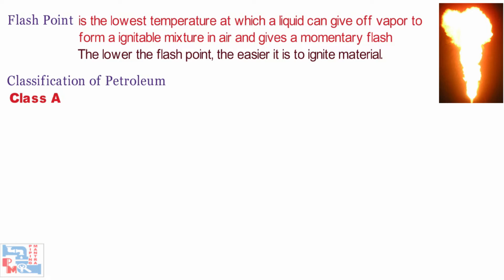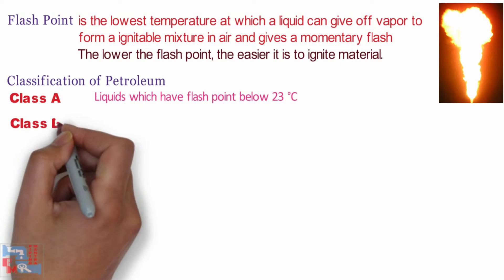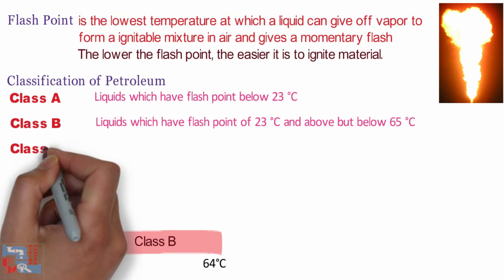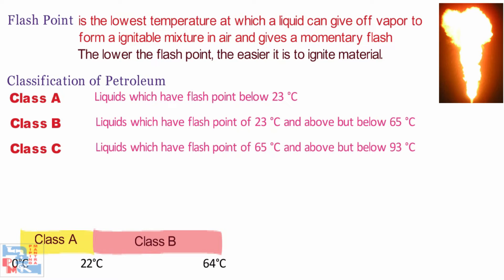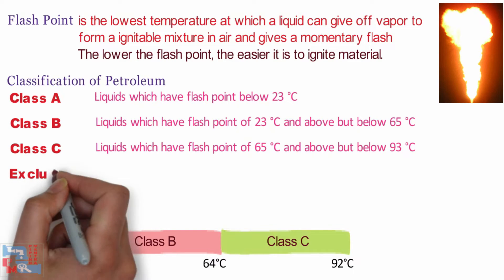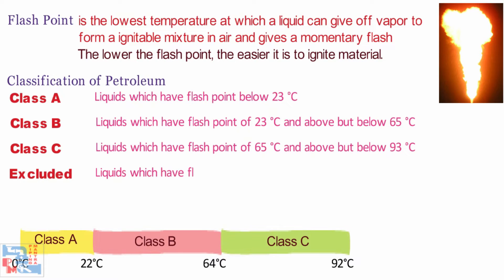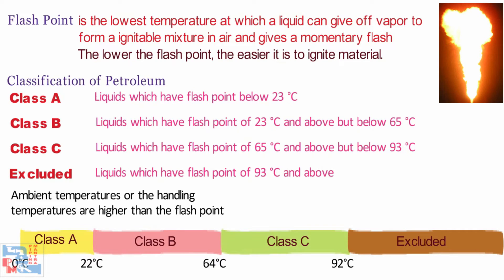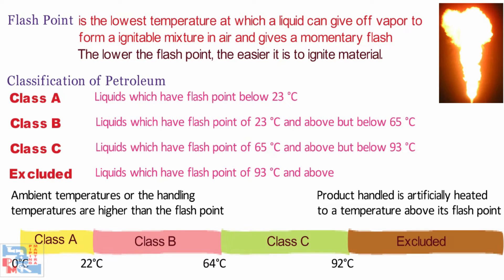Class A Petroleum are liquids which have flashpoints below 23 degrees Celsius. Class B Petroleum are liquids which have flashpoints between 23 and 65 degrees Celsius. Class C Petroleum are liquids which have flashpoints between 65 and 93 degrees Celsius. One thing to keep in mind is that this classification does not apply and special precautions should be taken where ambient or handling temperatures are higher than the flashpoint of the product, or where the product handled is artificially heated to a temperature above its flashpoint.